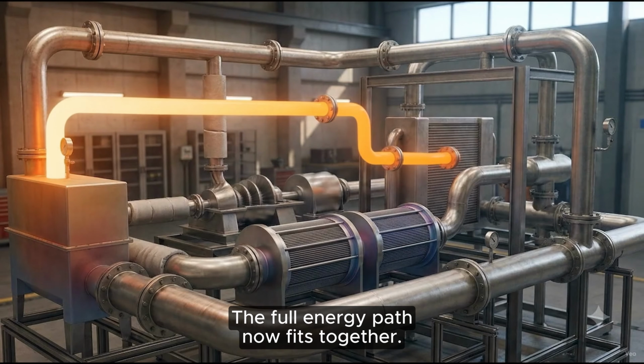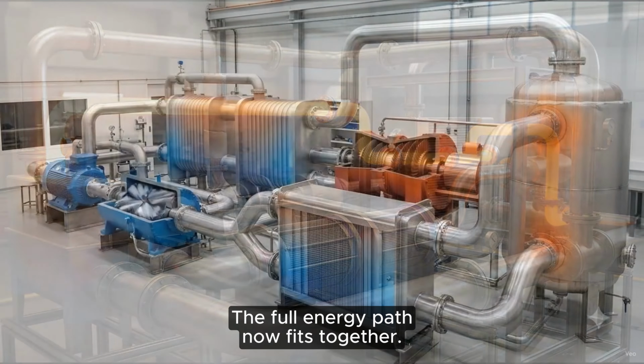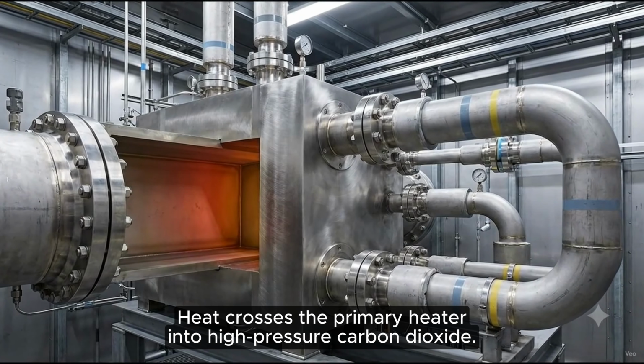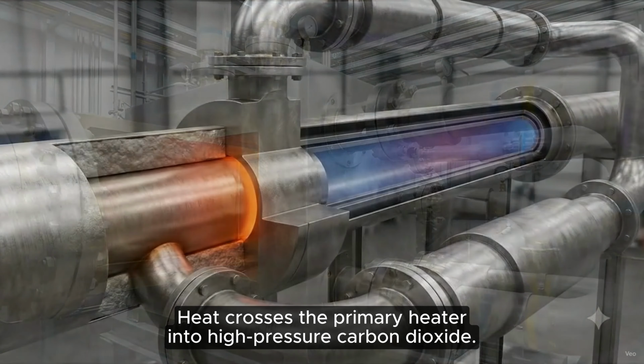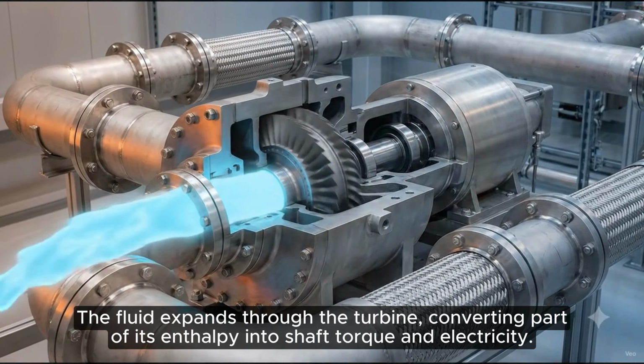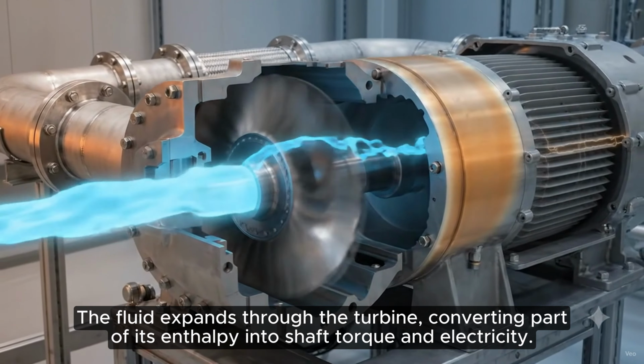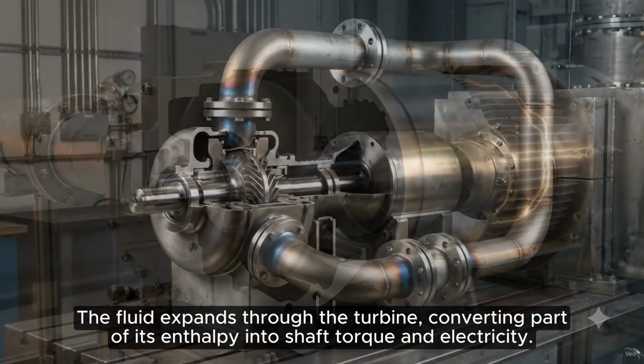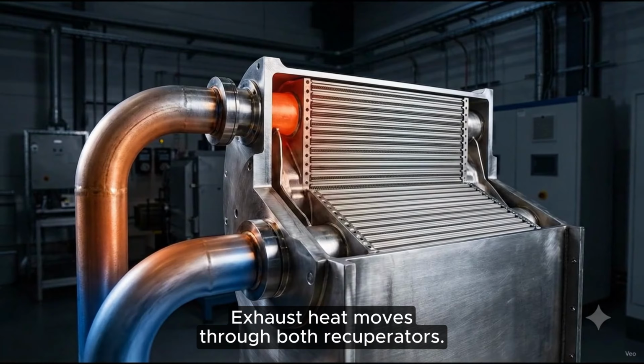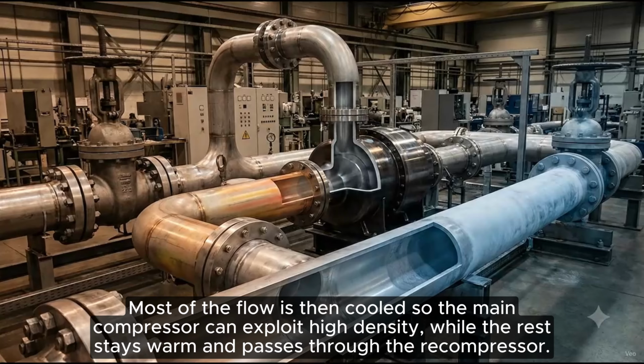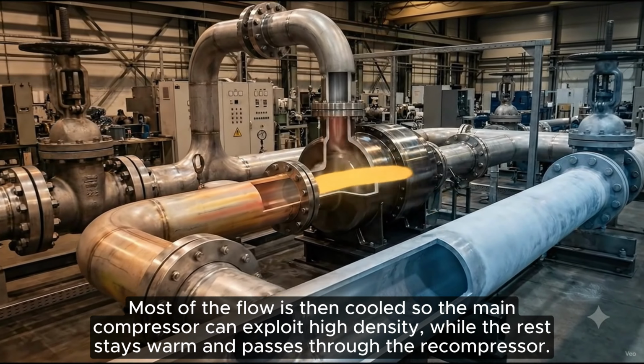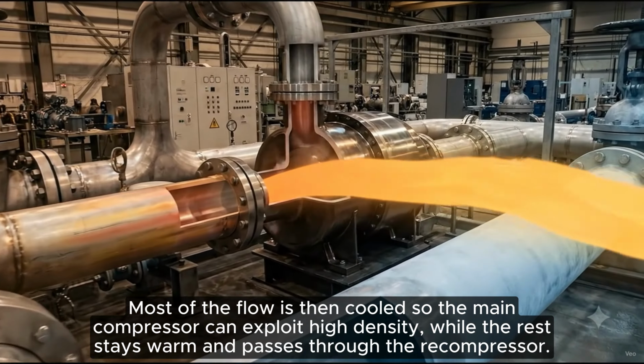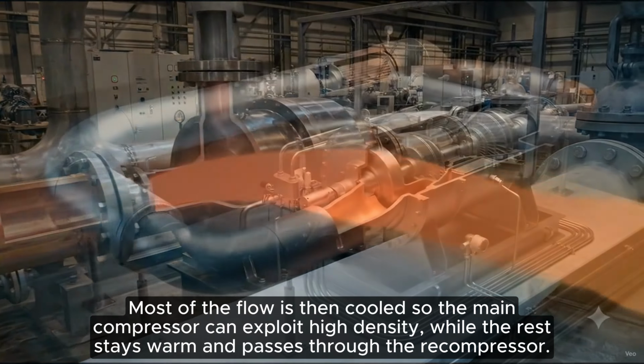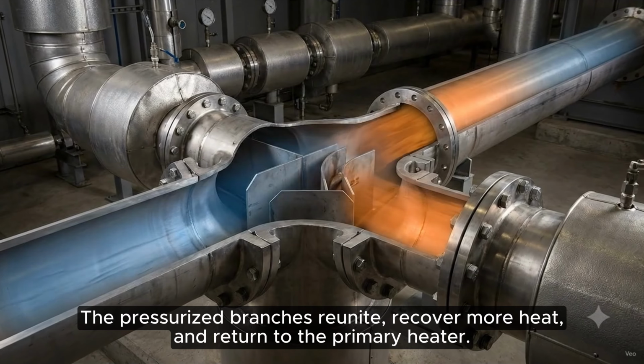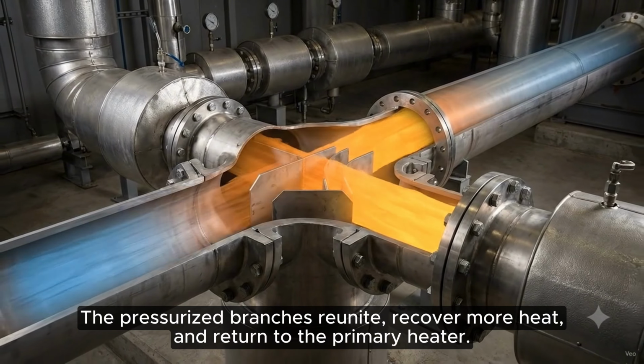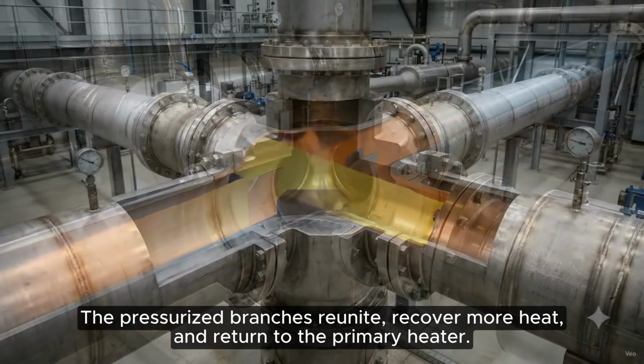The full energy path now fits together. Heat crosses the primary heater into high-pressure carbon dioxide. The fluid expands through the turbine, converting part of its enthalpy into shaft torque and electricity. Exhaust heat moves through both recuperators. Most of the flow is then cooled so the main compressor can exploit high density, while the rest stays warm and passes through the recompressor. The pressurized branches reunite, recover more heat, and return to the primary heater.